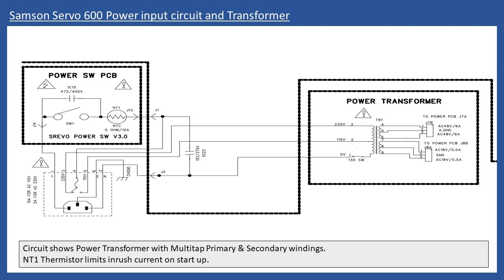So in my example there, you will have a fuse holder which is used for the 115 volt protection fuse, and there will be a cover over the top, but there's no fuse inside. What you find is the 230 volt fuse is fitted with the cover plate. What you don't want to do is remove that protection cover plate, the plastic plate, and put your finger on there, because lo and behold you're going to have 115 volts on there. And again, what you don't want to do is think, well, there's a missing fuse, and go and put one in, because as soon as you do that, you're effectively connecting that part of the winding into operation.